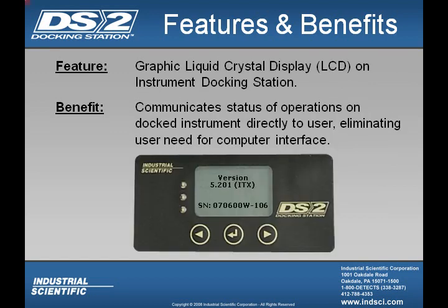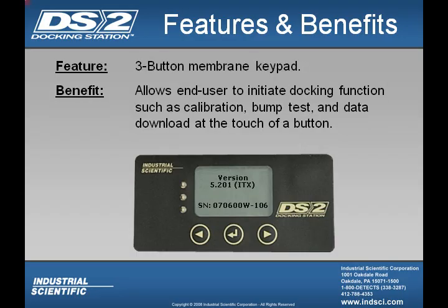Another feature of your docking station is the graphic liquid crystal display on the front of your DS2. And what this will do is communicate status of operation on docked instruments directly to the user. And this will help eliminate the need for a computer interface. You also have a 3-button membrane keypad, and this of course will allow the end user to initiate docking functions such as calibration, bump tests, and data download at the touch of a button.